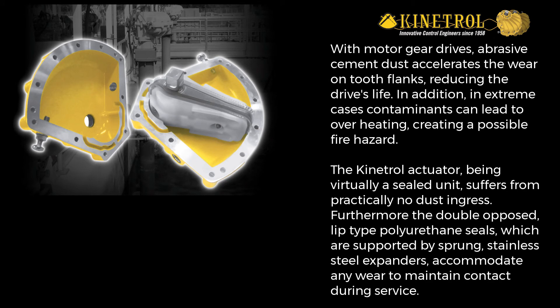With motor gear drives, abrasive cement dust accelerates the wear on tooth flanks, reducing the drive's life. In addition, in extreme cases contaminants can lead to overheating, creating a possible fire hazard.